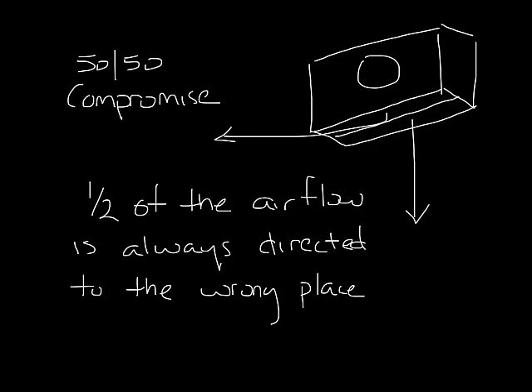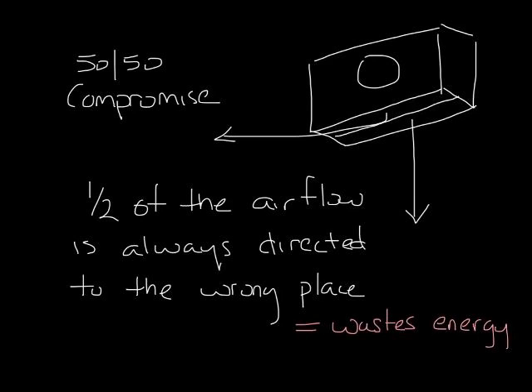This may be reasonably acceptable in cooling, but during heating this wastes energy because half the air that you paid to heat up will never reach the occupied zone. Now many slot diffusers are adjustable so the building owner or facility manager can move the pattern controller from cooling to heating position in the fall and then back to cooling in the spring. Let's face it, this probably doesn't happen in a lot of places.